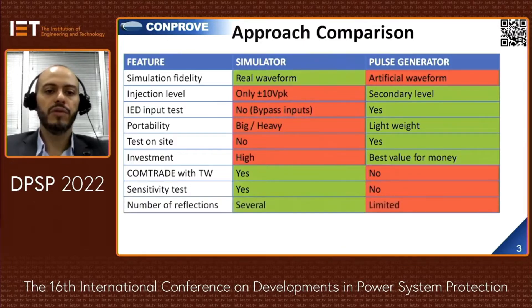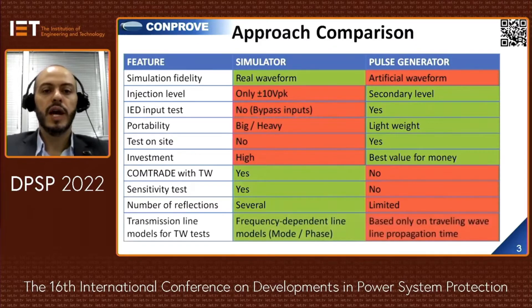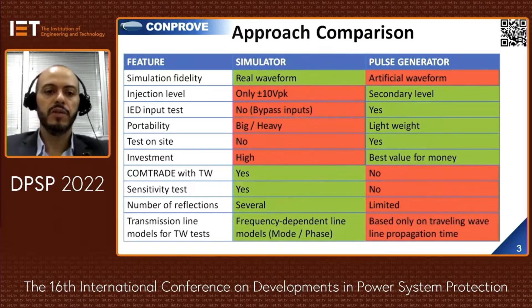About reflections, the simulator solution can reproduce several reflections, while the pulse generator uses a capacitor discharge that limits the number of reflections. Concerning line models, the simulator uses a frequency-dependent model; however, the pulse generator is based only on propagation time and does not have a complex and accurate model. You can see the pros in green and the cons in red.